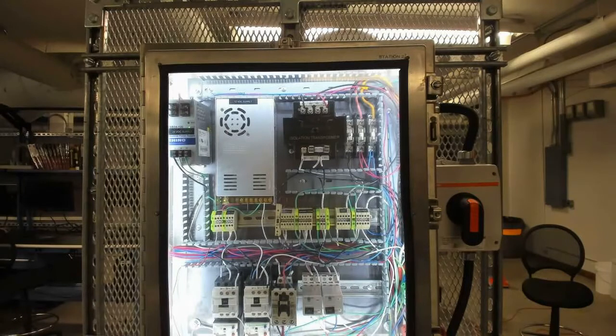This is the motor control center. It provides our control circuitry for the training skid. So our main power, which is 208 three-phase, comes into our primary disconnect. This disconnect is the on and off for the system. The 208 three-phase comes inside the motor control center, and we go into 3 fuses. Each of those fuses is protecting the hot. The 3-phase has 3 hots, A, B, and C. The fuses protect the branch circuitry.